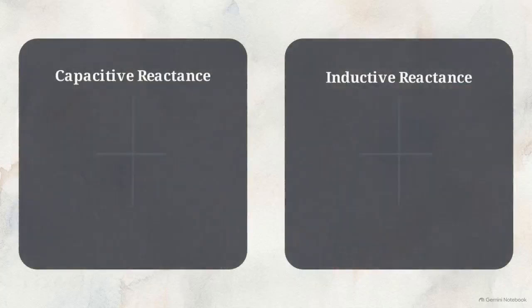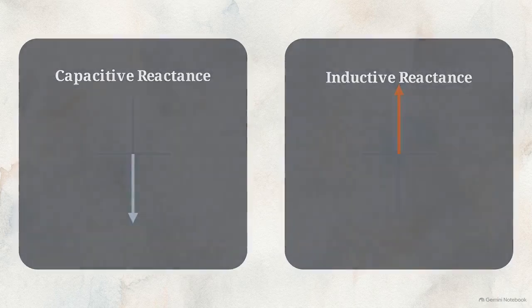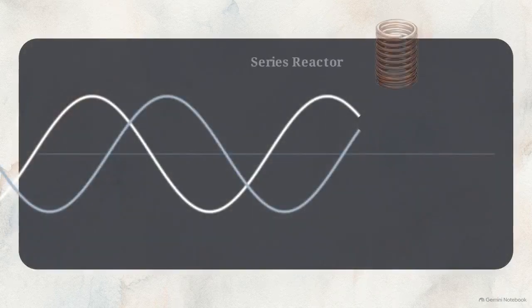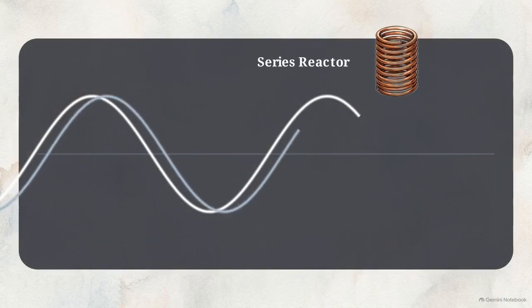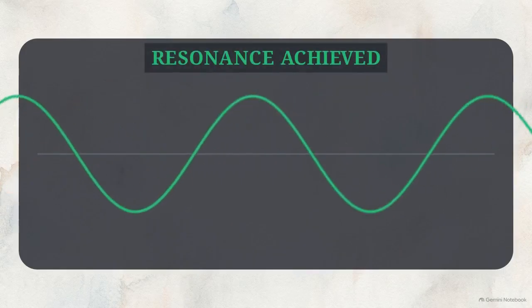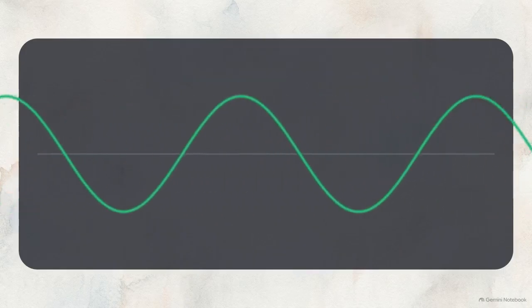In AC circuits, inductance acts in direct opposition to capacitance. The reactor provides the exact amount of inductance needed to cancel out the capacitive phase shift, pulling the signal back into resonance. Combining capacitive division with inductive compensation allows the CVT to output a perfectly timed replica of the grid, maintaining a strict 0.2 class metering accuracy.